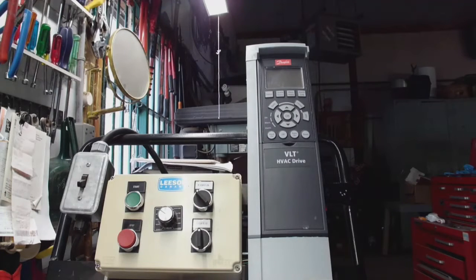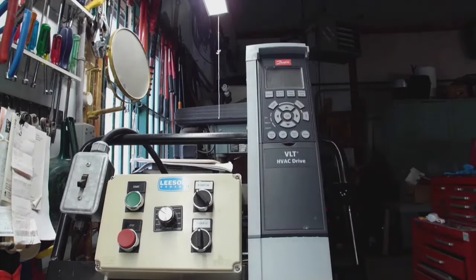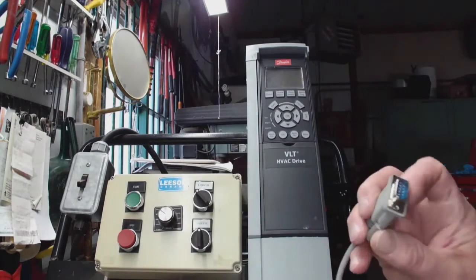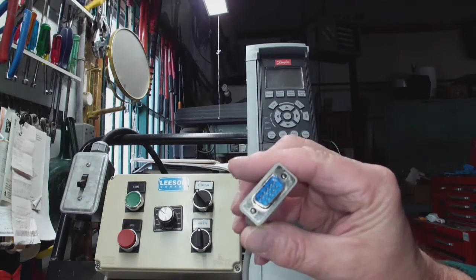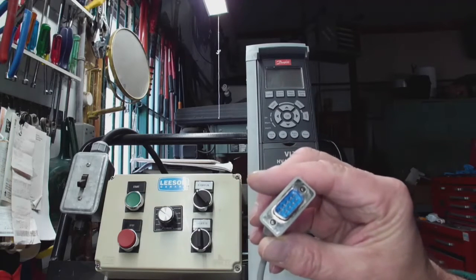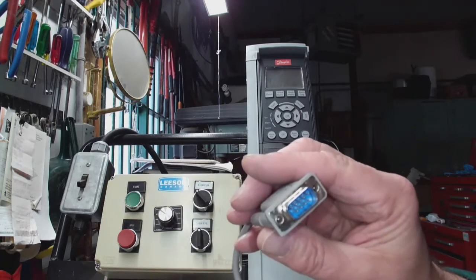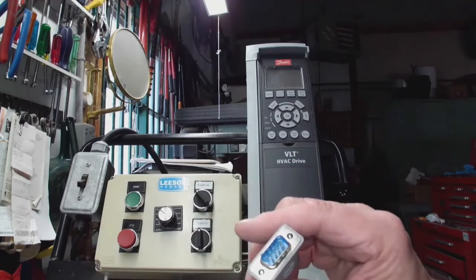The first thing we're going to look at is the LCP — this is called the local control panel. We're going to use it with an RS-232 communication cable. That cable uses DB9 pins — it's a male-by-female RS-232 connection, which means there's a communication format inside the drive. It can only go about 10 feet between the LCP and the actual drive itself.